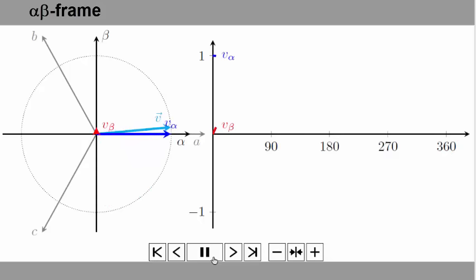These controllers in the rotating reference frame are, therefore, designed to control the direct and quadrature components of the space vector, although we now need means of measuring or estimating the angular speed of the machine. In the case of a grid-tie converter, we will need to track the grid frequency and phase angle. The transformations to the DQ frame are shown here in their matrix form. Notice that, along with the voltages, we will also need to input the current phase angle theta of the vector we are trying to track. In the case of a synchronous machine, this is the absolute rotor angle, which we can measure by using an encoder. In the case of a grid-tie converter, this is the phase angle of line voltage referred to the phase A, which we can track using a phase-locked loop, a PLL.